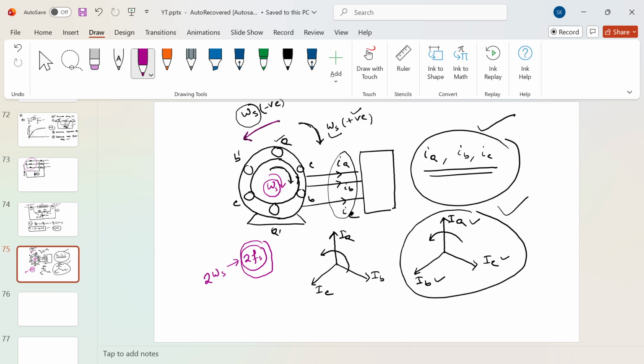And basically we don't use any kind of lamination in the rotor conductor, because the rotor is designed to handle the DC part. It is not designed to handle any AC component, because the rotor has only DC excitation, so we don't generally have any sort of lamination. Because of this, a voltage of twice the supply frequency gets induced in the rotor circuit, and in the rotor iron and rotor materials there will be huge core loss, because the eddy current loss and hysteresis loss depend on the frequency.